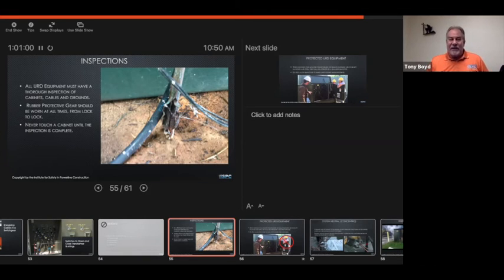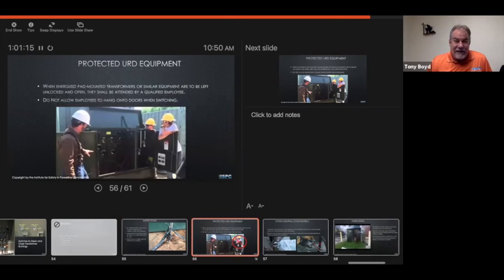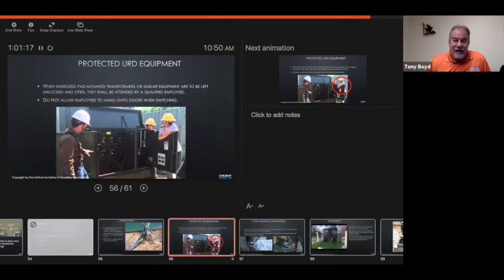Seven guys were in here just last week. And I said, well, this corrosion did not happen within the last week. So if you've been inspecting your ground rods, you have not been doing a very good job of it. And never touch a cabinet until the inspection is complete, and never let anybody hang on the doors. This is one of my big pet peeves. Do not allow employees to hang on to doors when doing any switching or doing anything. Keep them off of there.